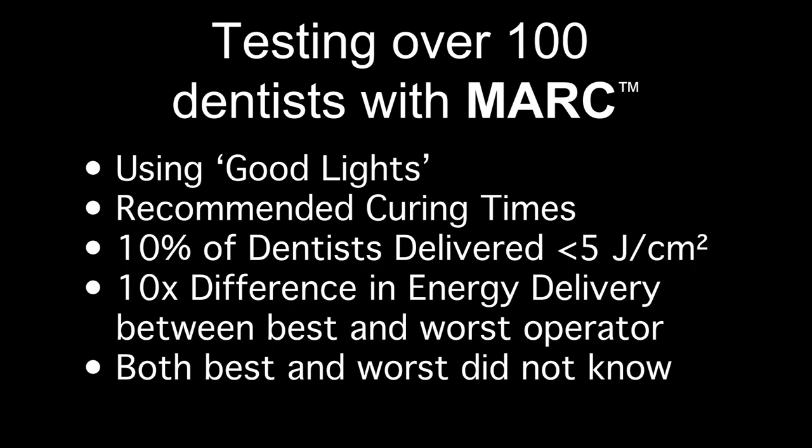We have tested over 100 dentists using MARC. Using good curing lights used for recommended curing times, 10% of dentists delivered less than 5 joules. None of the dentists knew how little energy they were delivering.